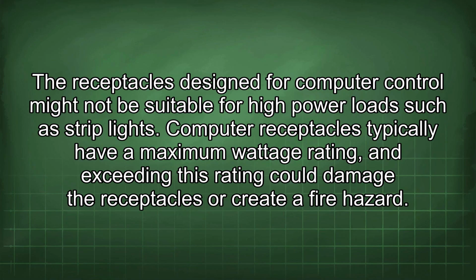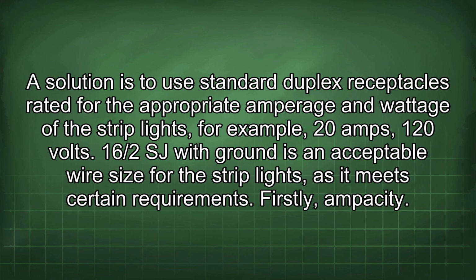The receptacles designed for computer control might not be suitable for high-power loads such as strip lights. Computer receptacles typically have a maximum wattage rating, and exceeding this rating could damage the receptacles or create a fire hazard. A solution is to use standard duplex receptacles rated for the appropriate amperage and wattage of the strip lights, for example, 20 amps, 120 volts.